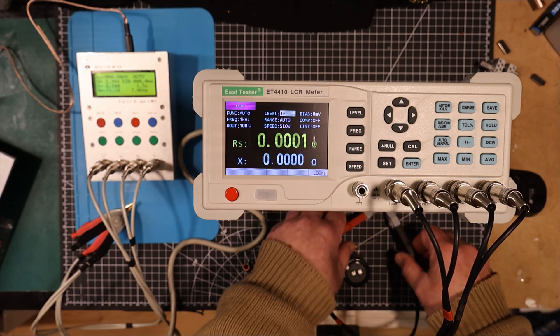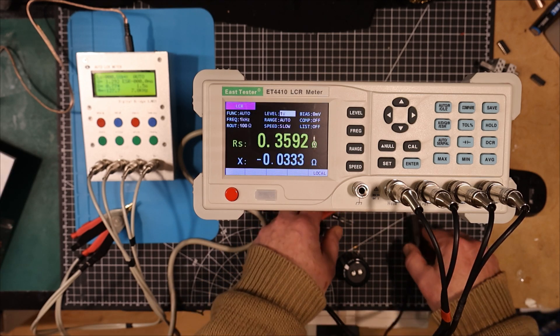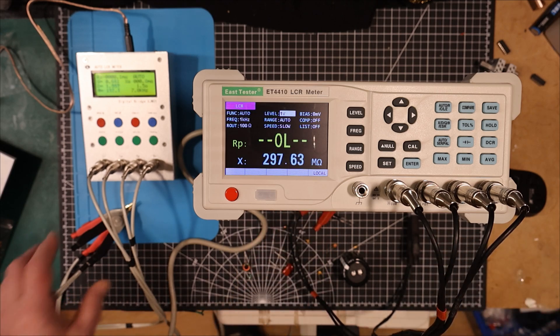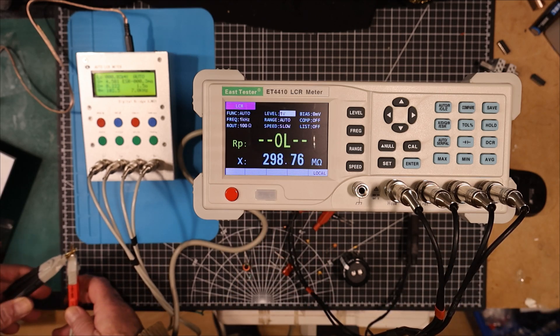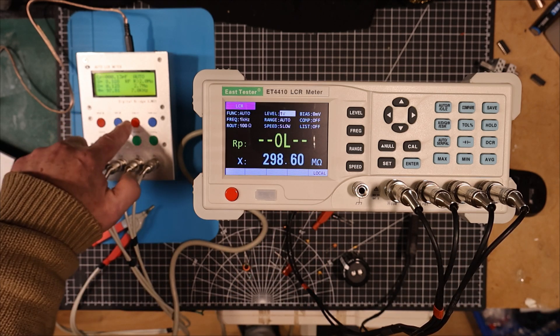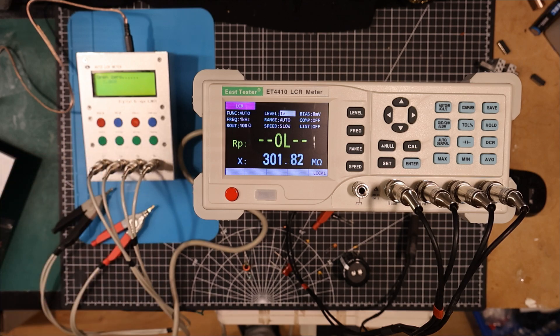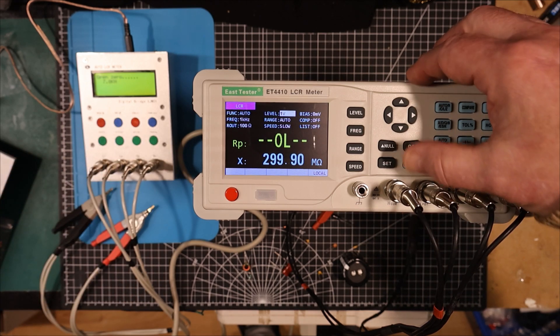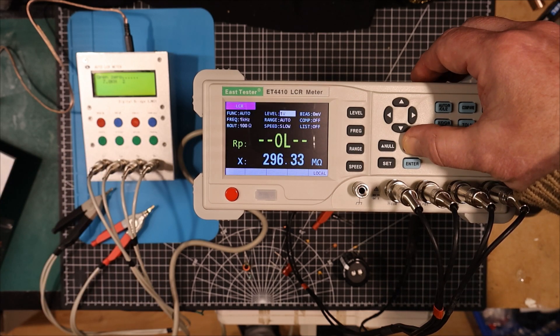Okay, that's the short calibration done. Now they recommend that you do the calibration every time you use the instrument. I'm going to start here the open calibration on this one. Open. And then we'll start the open calibration on this one.